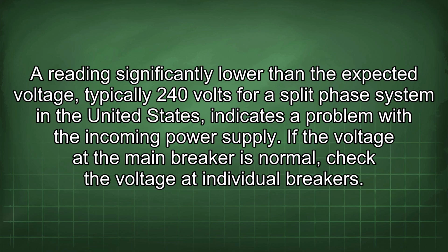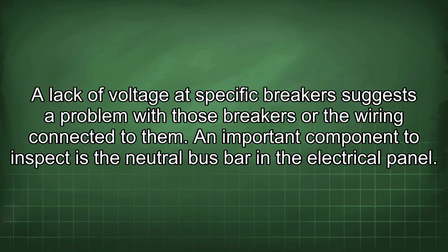A reading significantly lower than the expected voltage, typically 240 volts for a split-phase system in the United States, indicates a problem with the incoming power supply. If the voltage at the main breaker is normal, check the voltage at individual breakers. A lack of voltage at specific breakers suggests a problem with those breakers or the wiring connected to them.